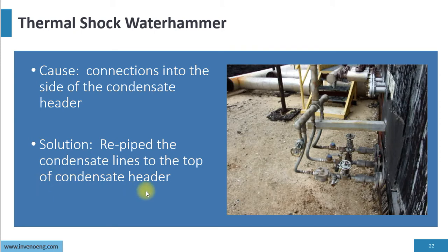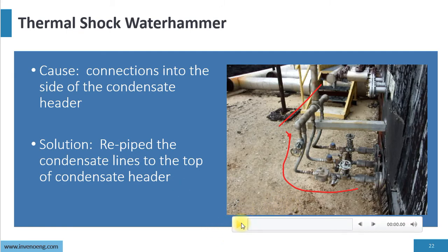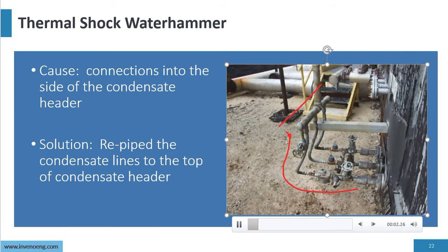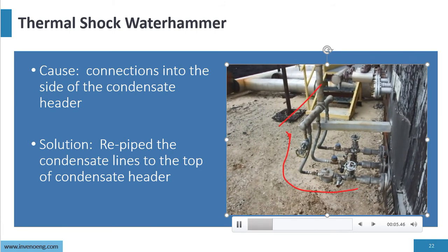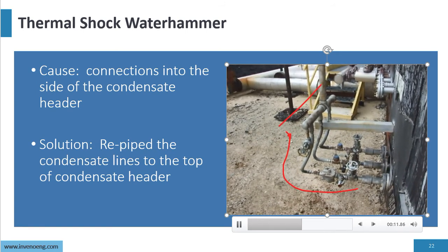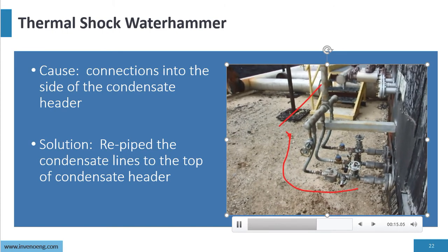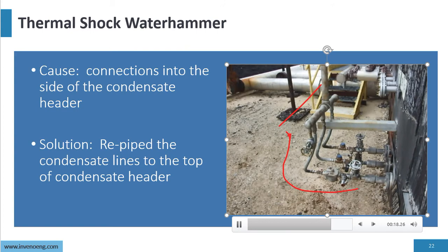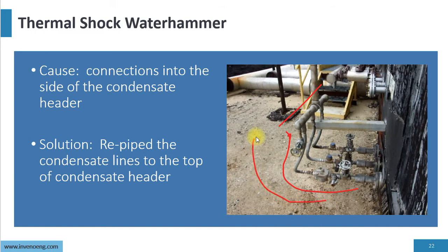This is just another application where the Waterhammer is coming off and coming into the bottom of a condensate collection header here, and again resulting in Waterhammer. Again, the solution would be coming off, repipe, and come into the top of the header, thus resolving the Waterhammer issue.